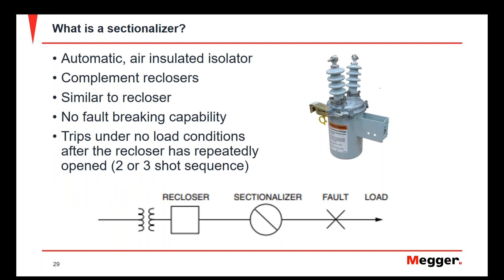In complement to a recloser, sometimes there's a sectionalizer. A sectionalizer is a device that also has a protective function built in, but it's not built to function under a fault condition — it's built to open whenever there's a no-load condition on the line. After the recloser operates, completes its shot sequence, and becomes locked out, the sectionalizer will open to isolate the rest of the circuit. If designed to do so, the recloser may then reset and close back in, depending on whether other branches of the circuit are involved in that power distribution system.